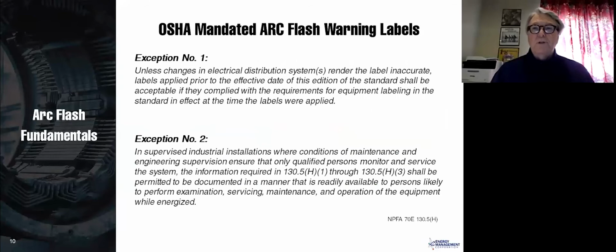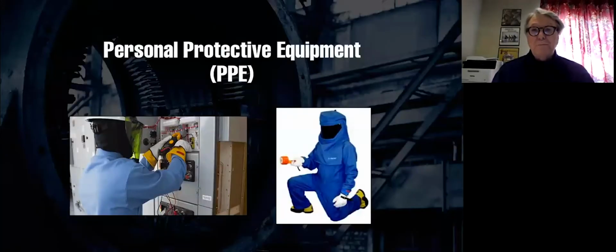Now, the exceptions to labels are if there's been some kind of a change to the system that made the original label inaccurate, then you must change it. And secondly, in supervised industrial installations where conditions of maintenance and engineering supervision ensure that only qualified persons monitor and service the system, then you can have that information in a different place. It doesn't necessarily need to be in a label on the equipment.